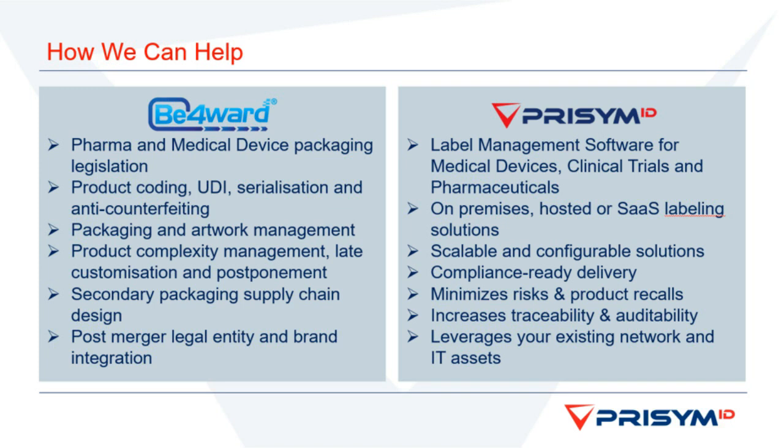So, as far as the actual labelling requirements are concerned, the EU MDR really is clamping down and putting some tighter regulation on that, and even more so than the US FDA regulations did. Now, a lot of these changes really are identified in Chapter 3 of the regulations, and so Chapter 3 is the requirements regarding the information supplied with the device. And in Section 23.2, that focuses specifically on the labels themselves.